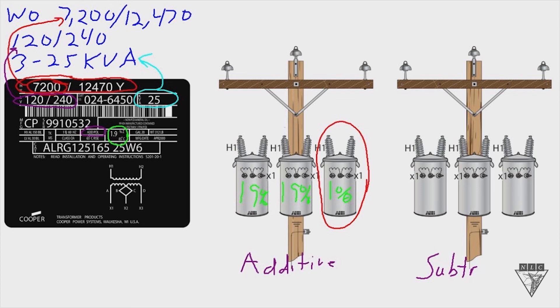So the reason why this is important is if you've got, let's say, two transformers that are additive and one transformer that's subtractive polarity, electrically you can connect it and make it work, but it's going to be a different type of connection than the traditional connection.